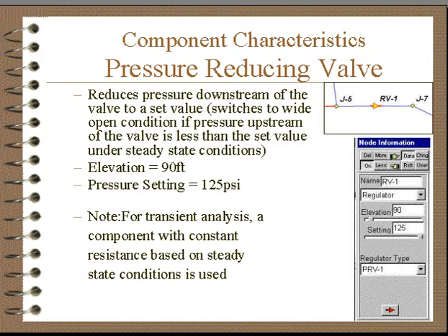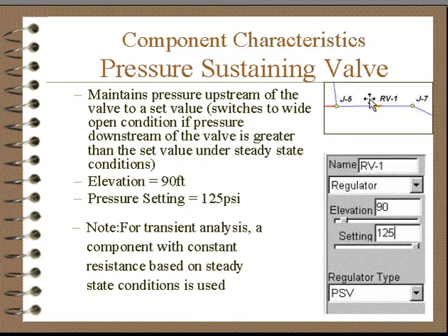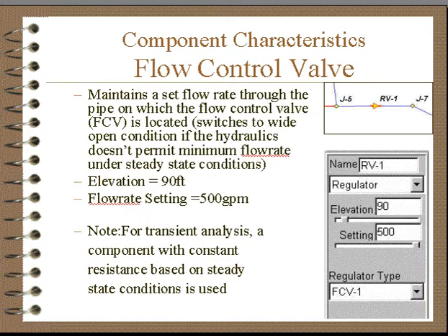We can also handle pressure reducing valves and regulating valves — these are all handled the same way. The steady state calculations are made and then the resistance of the valve is calculated based on the steady state condition, and a constant resistance is used. That's true for a pressure reducing valve and for a pressure sustaining valve. Whatever the pressure drop is at the given flow, we calculate the resistance and utilize that resistance.